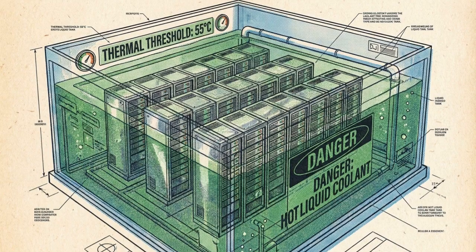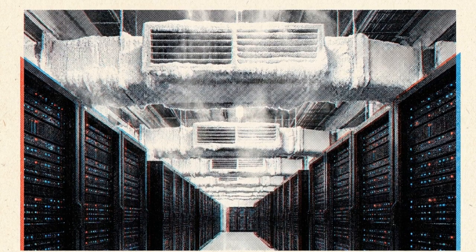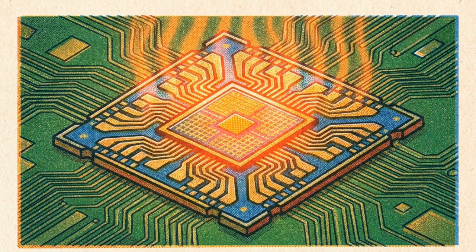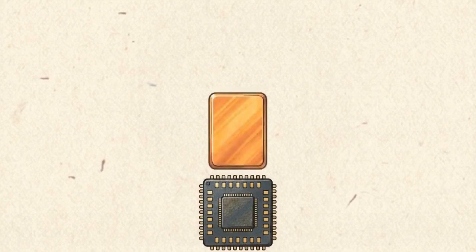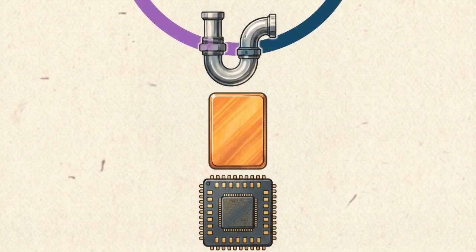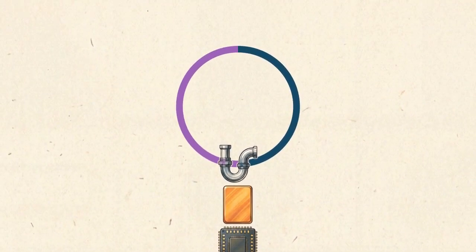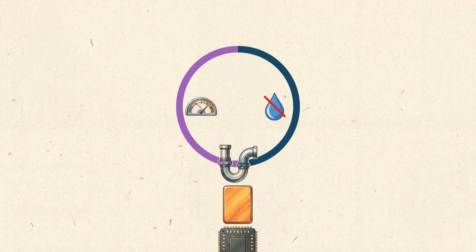To break out of this cycle, the industry is pursuing extreme alternatives. The first logical escalation is to stop wasting energy air conditioning a massive warehouse and instead target the heat exactly where it's generated. Looking at a simplified cross-section of a microchip, we can see how direct-to-chip cooling works: a water-based liquid coolant circulates across metal plates, usually copper or aluminum, attached directly to the processing chips. Because liquid is much denser than air, it absorbs and moves heat far more effectively. This closed-loop system cuts the power used by server fans by up to 80% and requires zero on-site water consumption to operate.